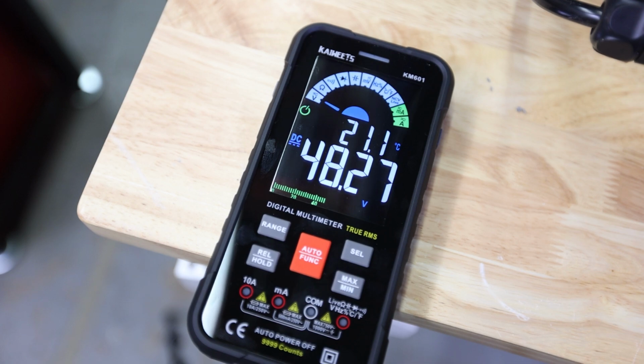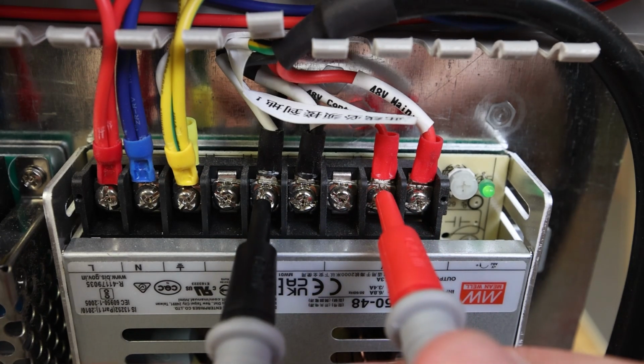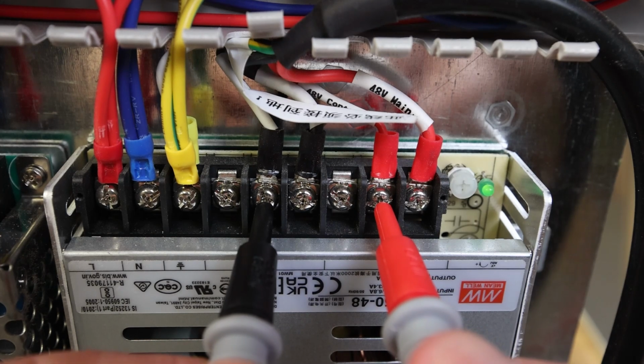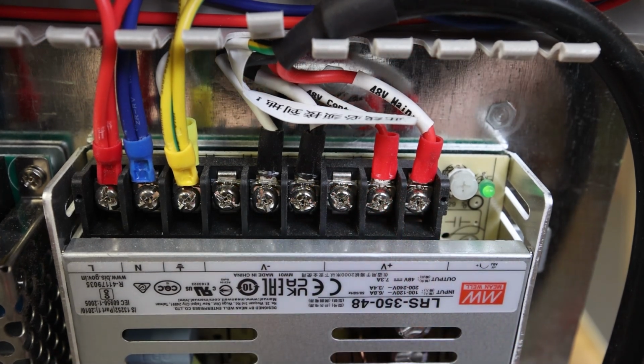If for some reason you probe the terminals backwards or connect your probes to the multimeter backwards, you may see a negative voltage instead, such as negative 48 volts in this instance. Don't worry, that result is still perfectly valid. So we found our 48 volt power supply for our laser source. The process is exactly the same for the remaining power supplies inside our case.